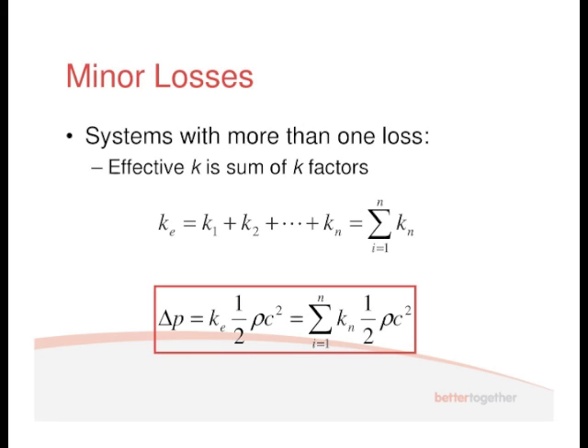That symbol there, this symbol here, sigma. That's the sum of all your K terms. And so your pressure drop due to these components, just due to the components, so this doesn't include friction, is going to be KE times by the dynamic pressure. The sum of all those terms multiplied by the dynamic pressure.